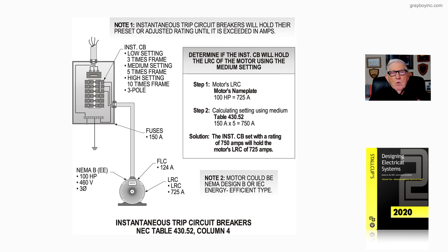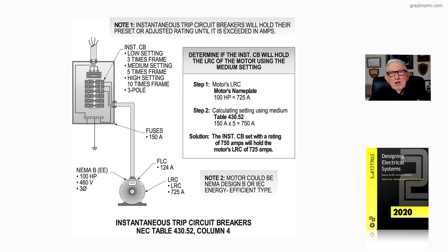If you didn't want to use 1700 percent under Exception 430.52(C)(3), you could use a solid-state starter to reduce the starting current, or an adjustable speed drive in many cases. By adjusting the starting current with those methods, these percentages and settings can be lower. That's what we're illustrating here along with the text in chapter 18 of the electrical design book.